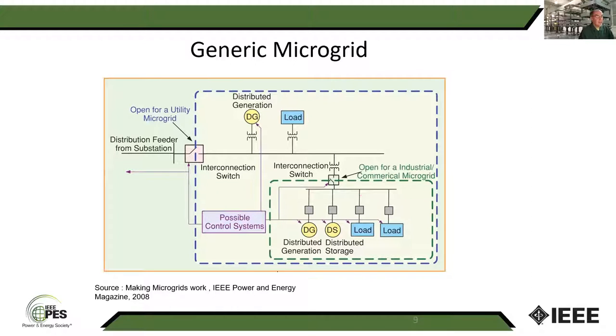And so within this system, usually you're going to have some sort of a control system that's going to manage this system, and that can affect the set points for the generation, possibly shed load if the load exceeds the generation. And in some cases, you may have a very centralized control. In some cases, you have a more decentralized control. And so you see both types of things. So you may see a frequency droop scheme for how the power sources may share load, similar to how generators on a large grid share changes in load. And you may also see a voltage droop scheme for reactive power. So there are a number of different ideas people have looked at, and there are different degrees of communication and control available with these. Generally, what you see is the ones that have been installed in the field tend to have simpler control schemes. The ones that are written about in academic papers tend to have much more complicated control schemes.